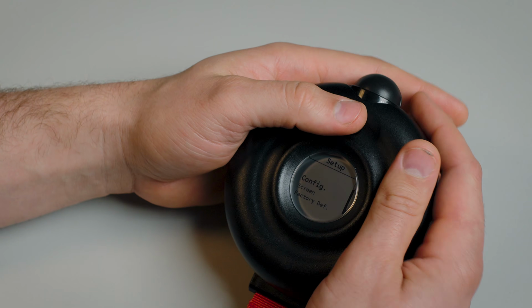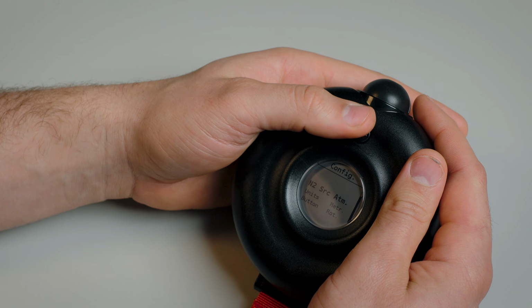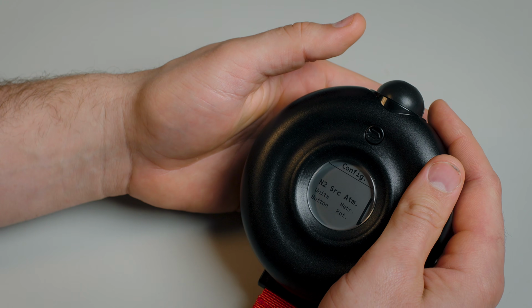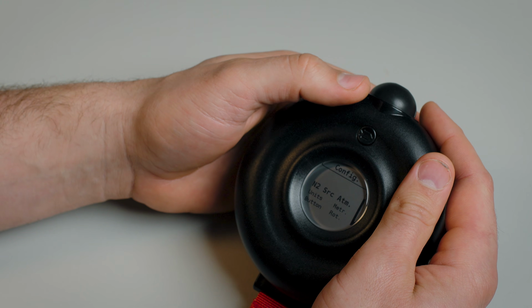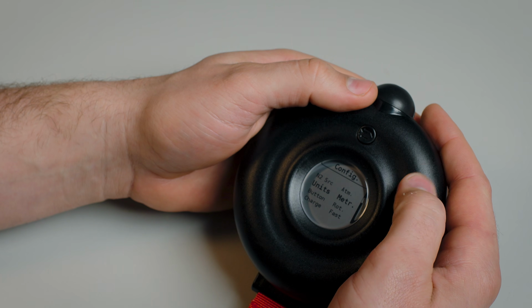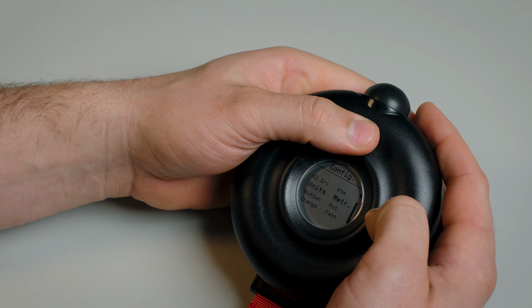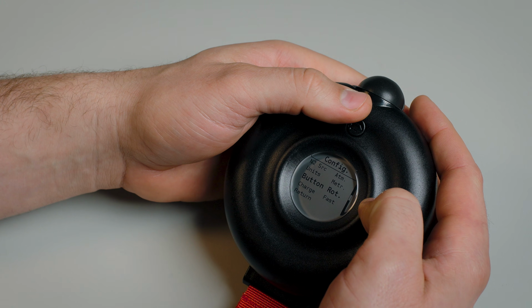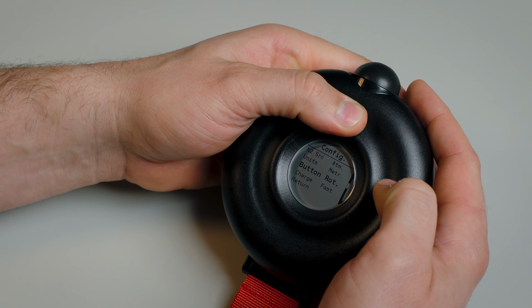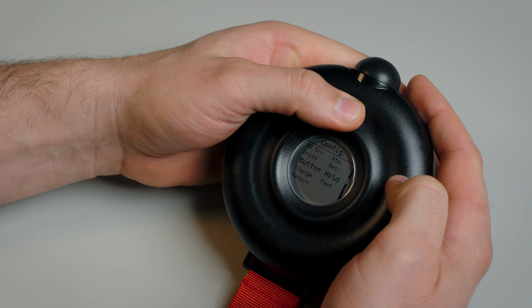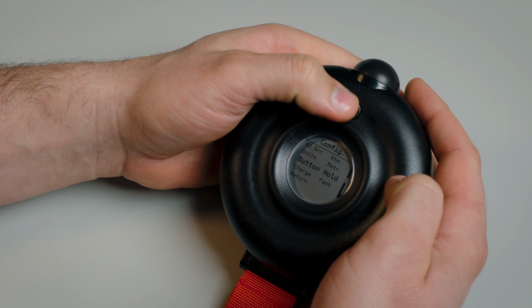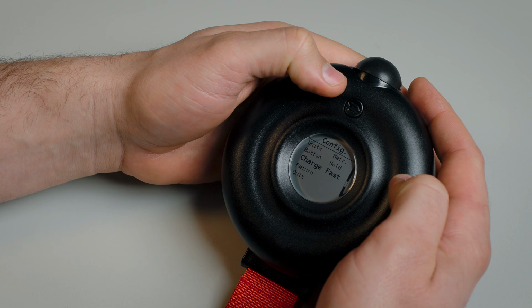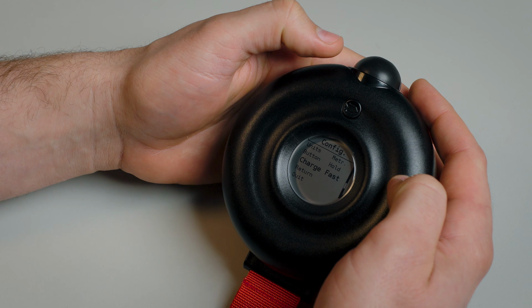Now let's talk a little bit about the setup. Here we can configure our device to see if we, for example, want to use the atmospheric nitrogen or if we have a source of pure nitrogen. We can select if we want to use metric or imperial units and what the short press of a button does in the main screen. We can, for example, rotate it, have it do nothing, or hold the measurement that we have just read. Next is the charge. You can either have your device fast charge or slow charge. The slow charge will conserve your battery a little bit more, giving it a longer lifetime.